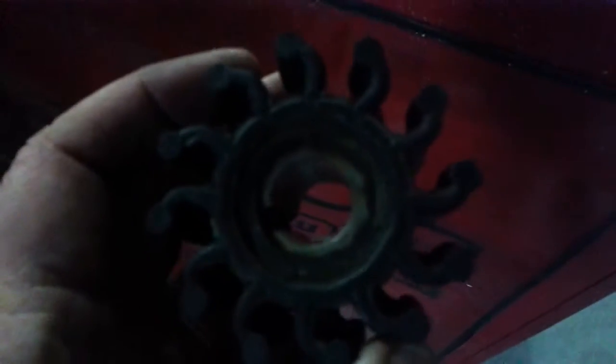We'll show you the hoses first. It's time to replace a few hoses. I think this is the inlet hose. Yeah, this is your inlet hose. You can see all the cracking. Then this is the impeller from one of the pumps. These vanes aren't relaxed anymore, so this would probably have some reduced pumping, but still be pumping.